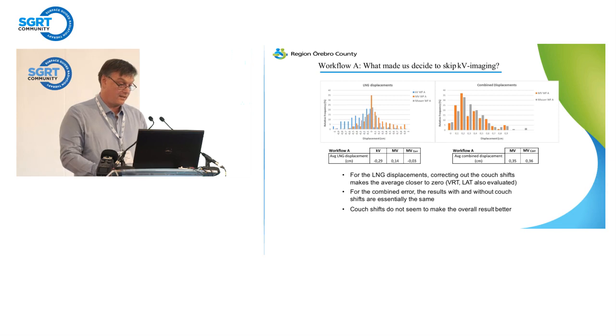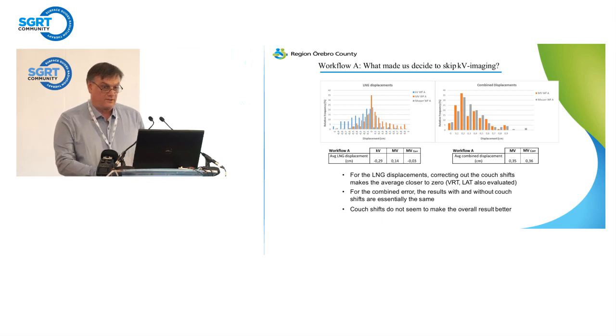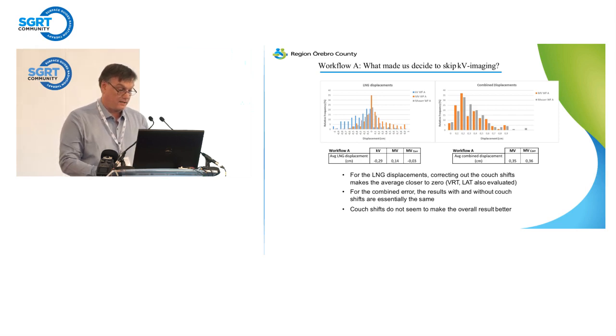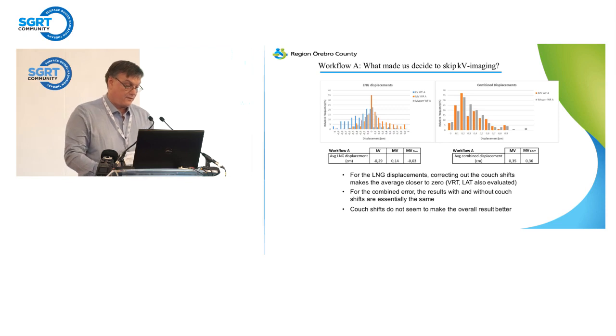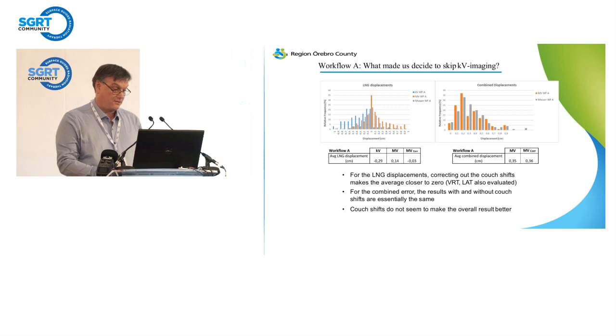We also looked at vertical and lateral displacements with similar results. We also looked at the combined displacement — the resulting magnitude combining vertical, lateral, and longitudinal — shown in the histogram to the right. Looking at the average and the distribution, to a very high degree it looks like, in our workflow at least, the results with and without couch shifts are basically the same. There is not much of a difference. This leads us to the conclusion that in our situation, doing the couch shifts actually didn't really improve the treatments.